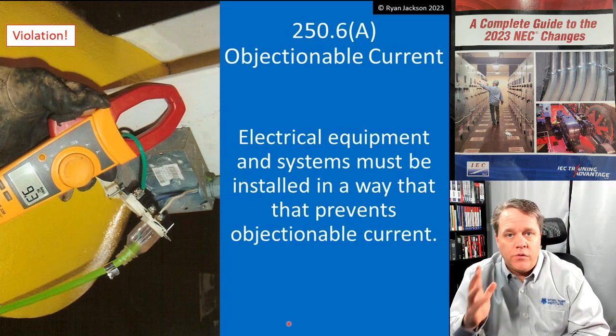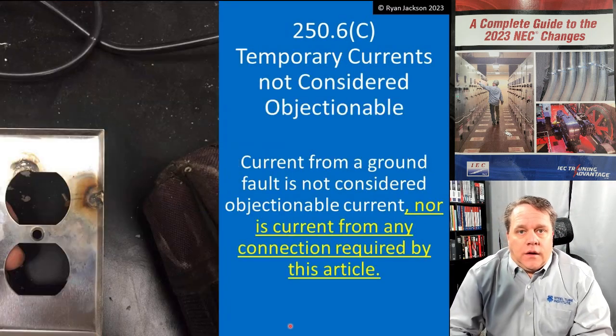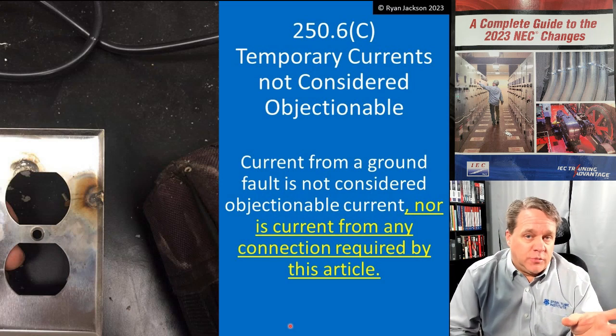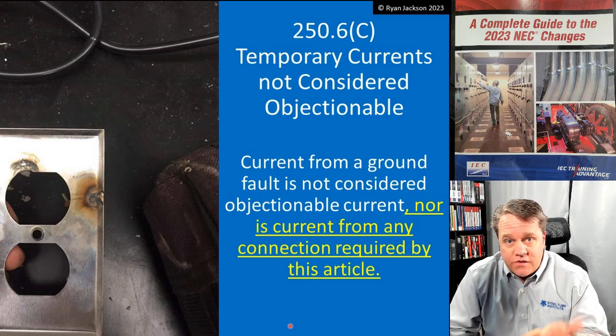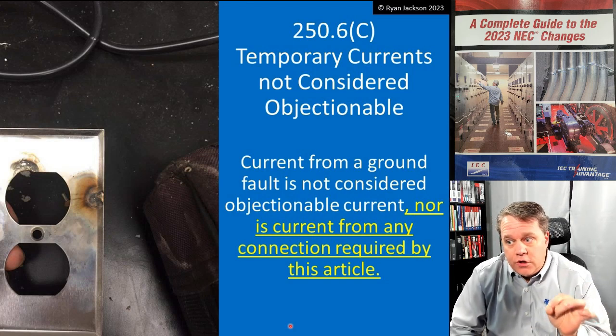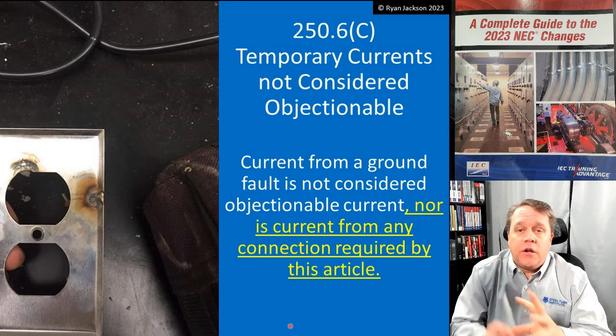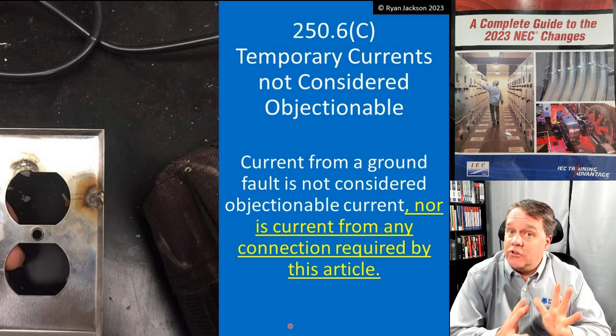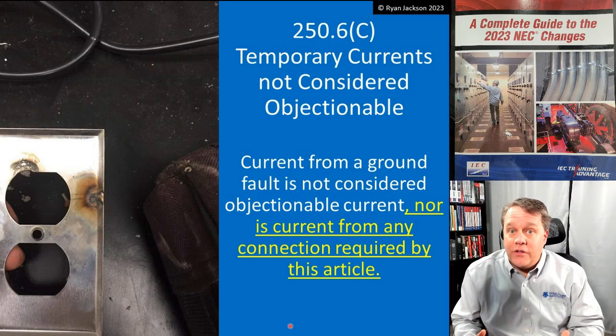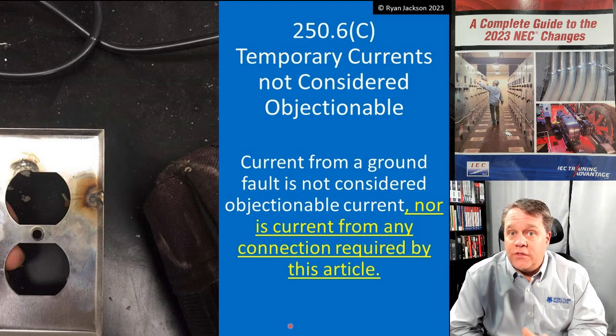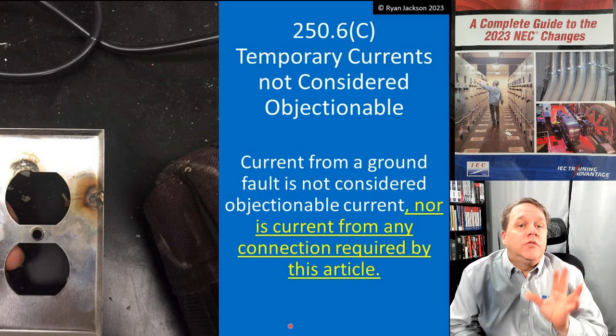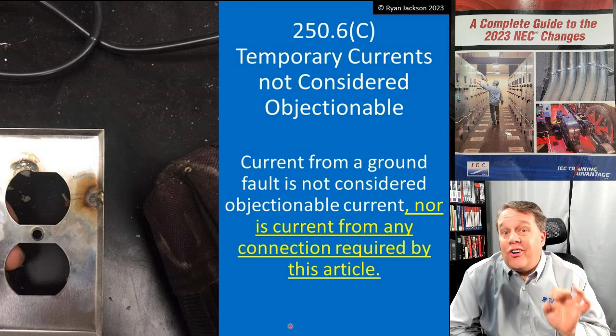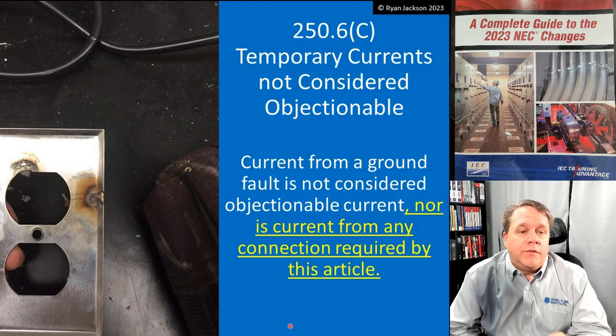Section 250.6(a) says you're not allowed to have objectionable current. Section 250.6(b) says if you have objectionable current, you need to disconnect equipment grounding conductors or disconnect the parallel paths. But it also says you're not allowed to just disconnect everything — you have to still ensure that the installation is safe. Now 250.6 also tells us what currents are not considered objectionable current.